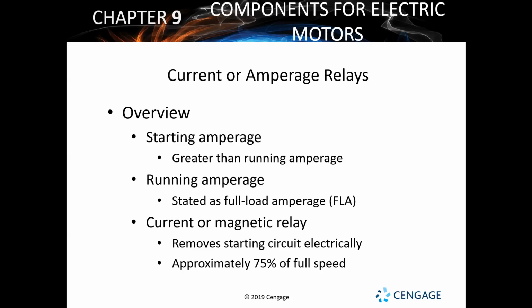Typically, your starting amperage is going to be about 5 to 7 times greater than your FLA. Not always, it depends on the manufacturer. Sometimes they make it 10 times greater, that starting amperage, and then it's going to cut back to a really, really low running amperage. You're seeing it more nowadays where DC electric motors are becoming commonplace, and they run on inverter technology, so they can vary their speed, but they're still taking in a lot of electricity. They're taking in a lot of AC electricity and converting it to DC. But the ability to control the speed and vary it is what makes them more energy efficient.